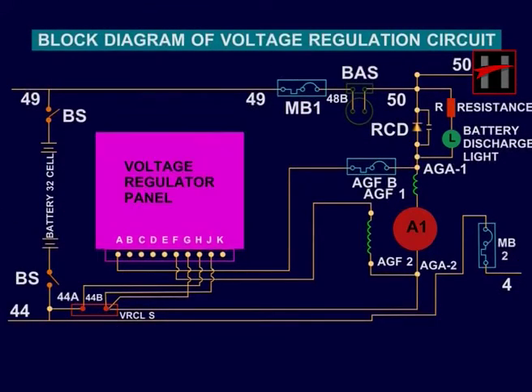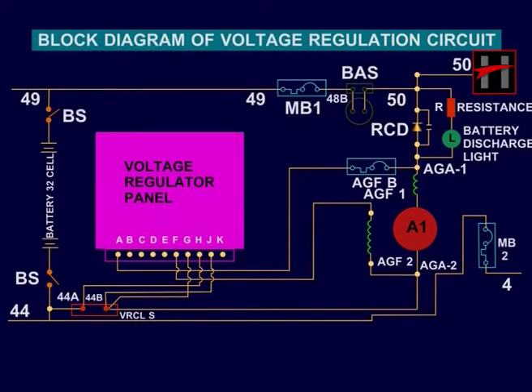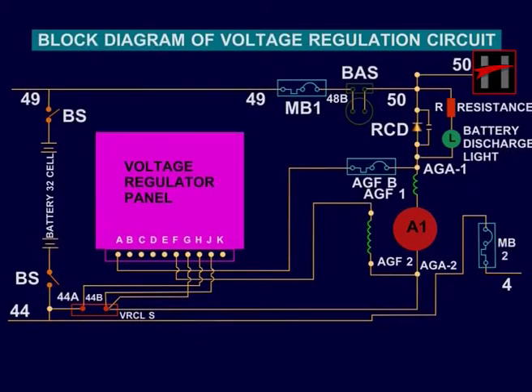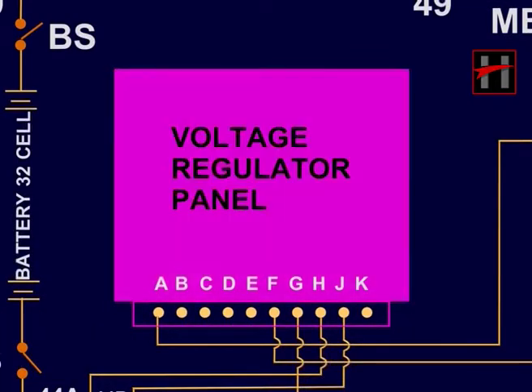The voltage regulator panel contains two drawer type cards. The small semiconductor components are attached to the two cards, while the large components are attached to the housing. All connections between the cards are made with plug-in type terminal blocks on the back edge of each card. The two cards are identified by the letters BN and BX; card BN is called the regulator card.